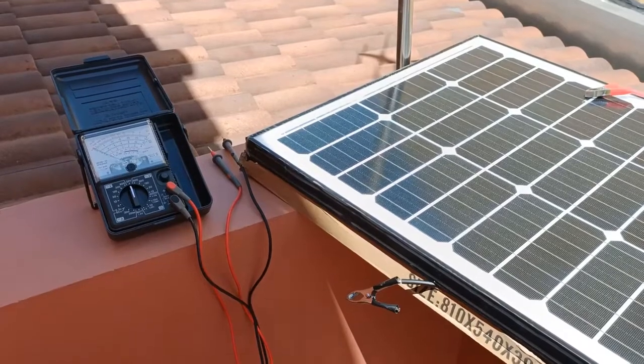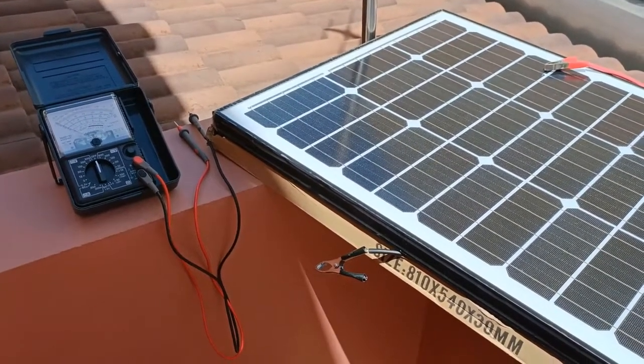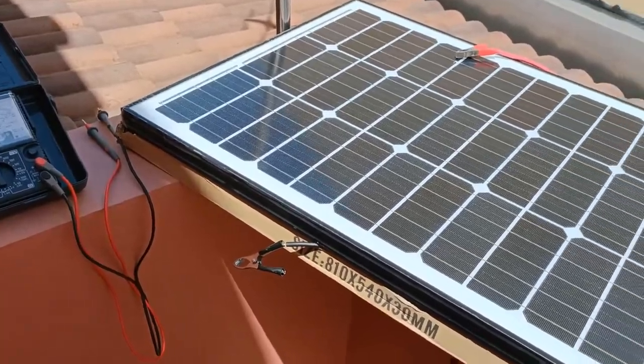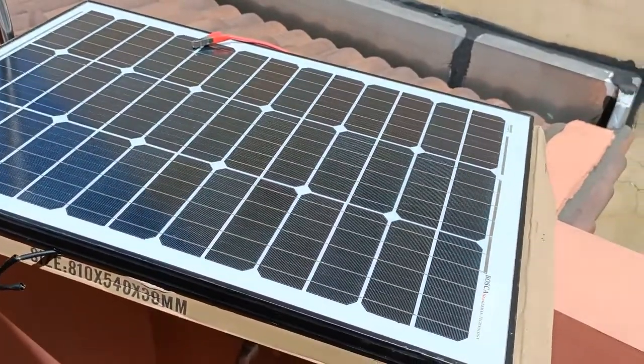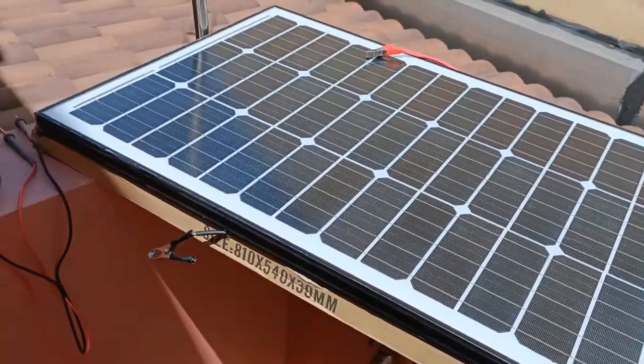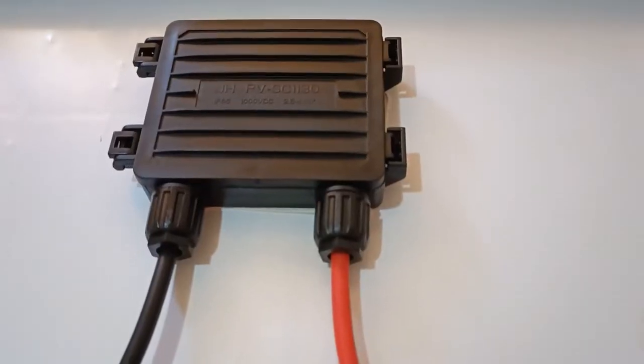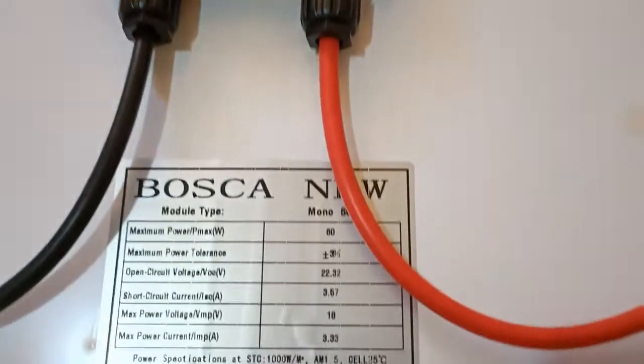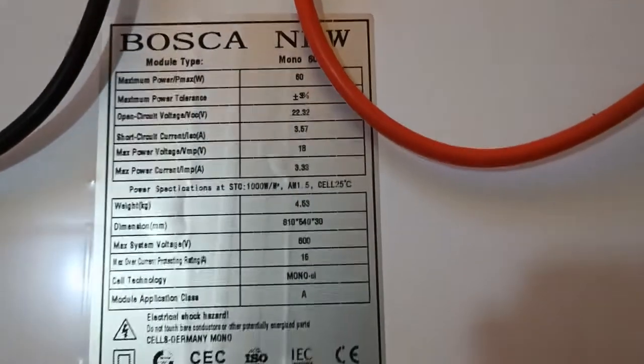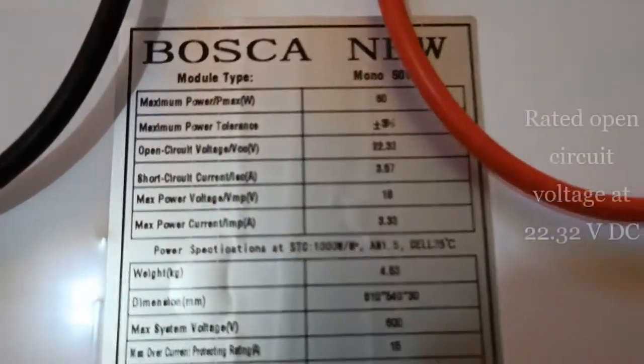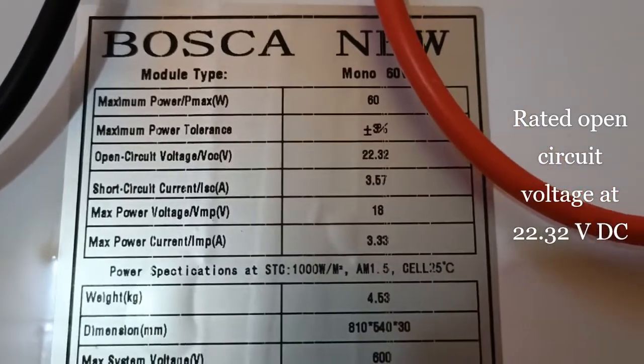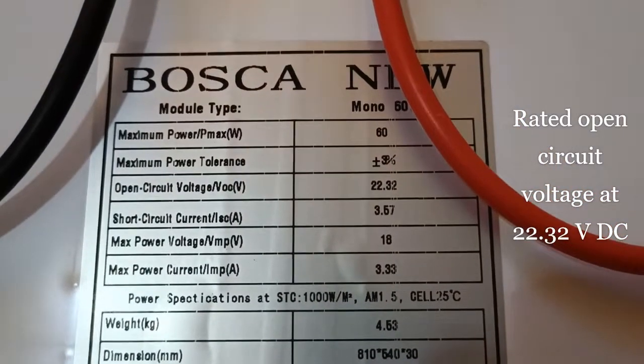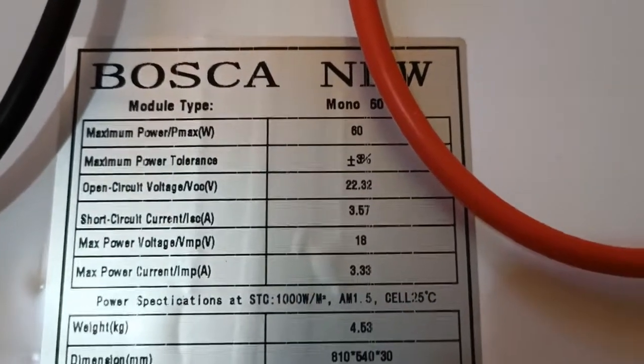This is my setup for testing the DC range function of the Hioki 3030-10 with regard to the output voltage of my 60W solar panel, Bosca solar panel. This is the back of my 60W solar panel. And this is the nameplate. And the nameplate ratings. As you can see the rated open circuit voltage, the maximum open circuit voltage is at 22.32V.